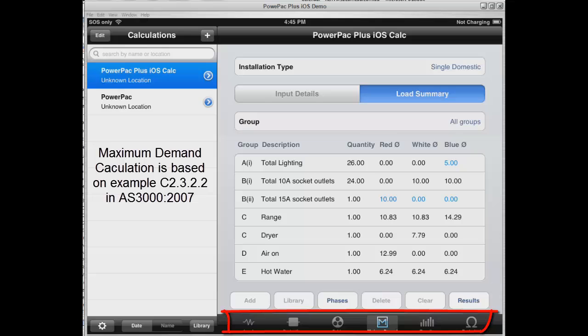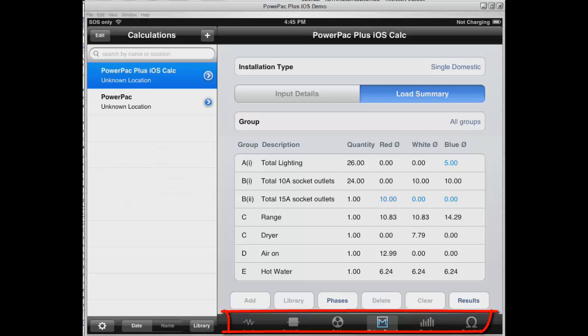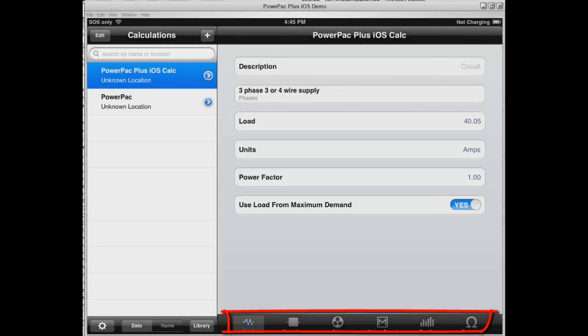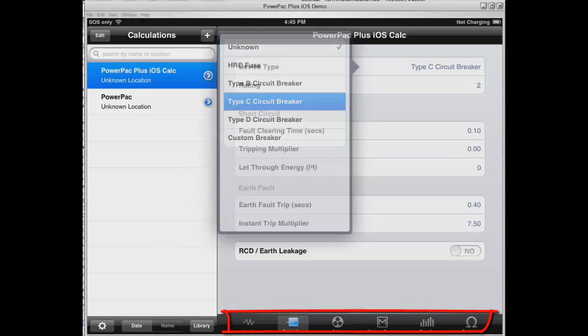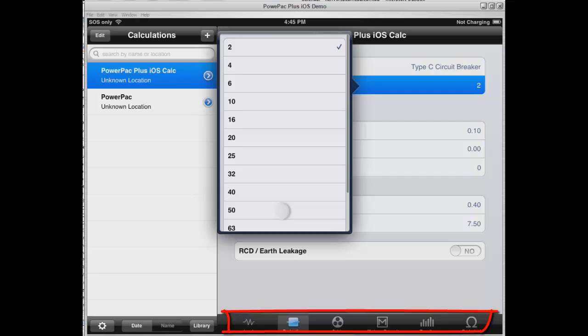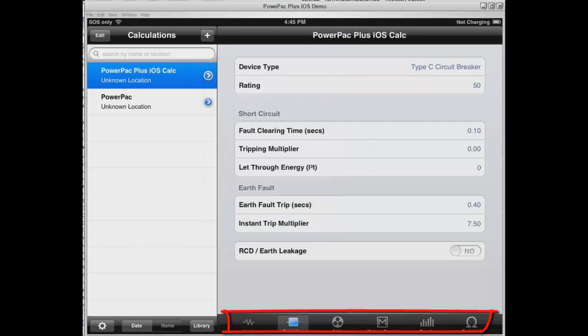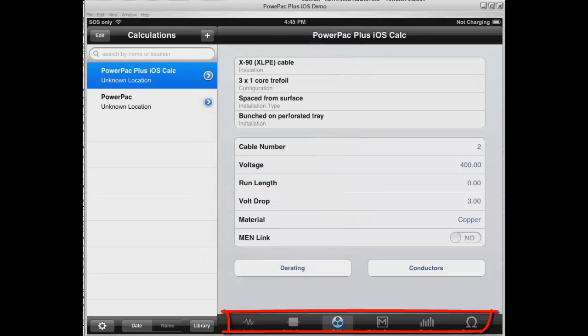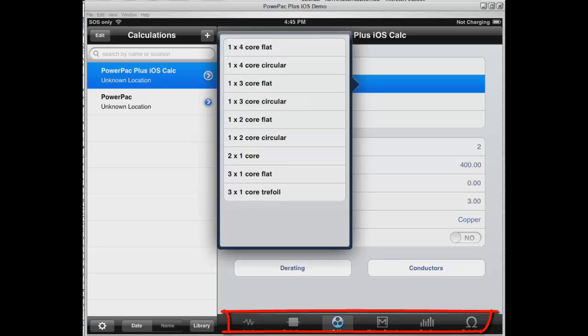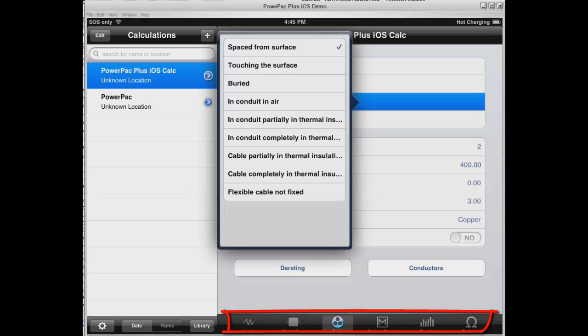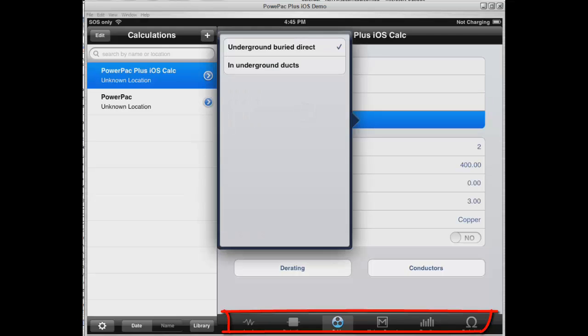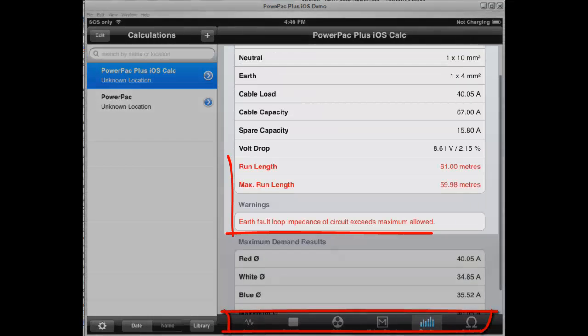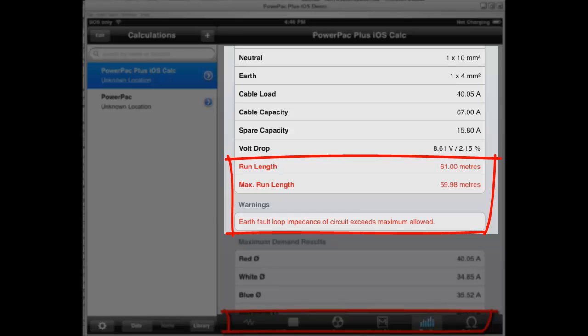We now want to size the cable from this. We're going to go to our load details and use load for maximum demand, which will bring the load across to 40 amps. We're going to go to our protection device and load a type C circuit breaker, rated at 50 amps. We're now going to select our cable. All cable selections are available from AS3008 and are selectable from this screen. We've got an XLPE cable — we're going to do a 3x1 trefoil, bury it underground in ducts in conduit, and run it at 61 meters.